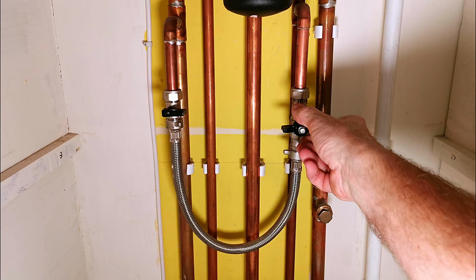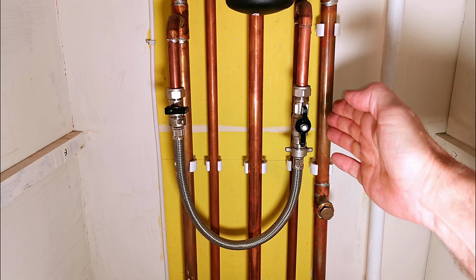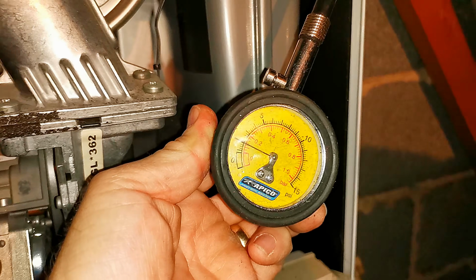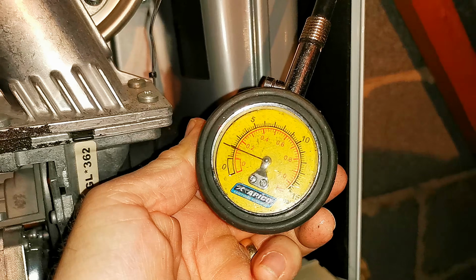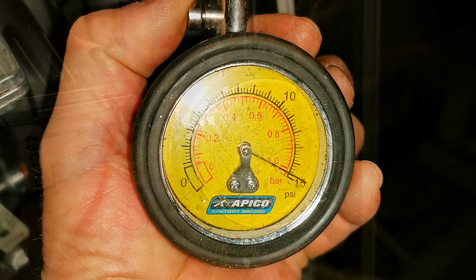I'll go into a bit more detail on topping up your boiler on the other pressure sensor in just a minute or two. I thought I'd just mention, whenever I get the boiler drained down, I always check the pressure vessel and recharge it if necessary.